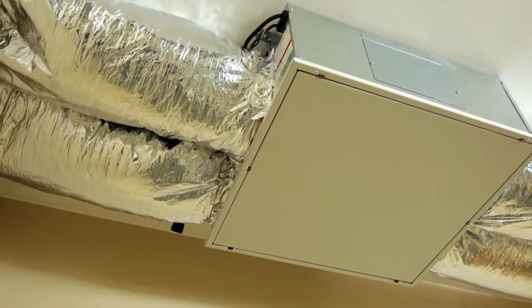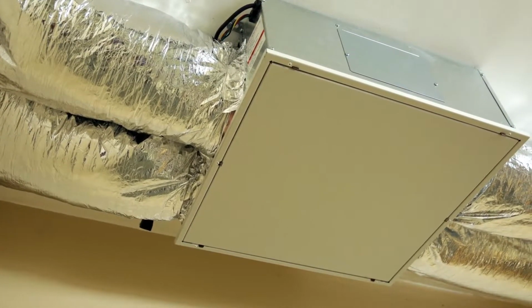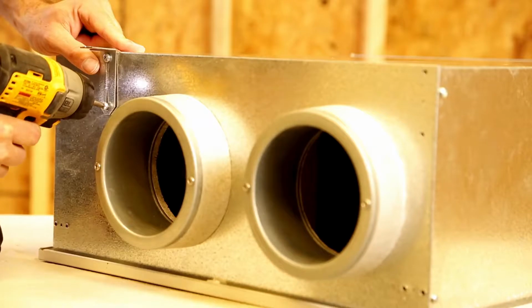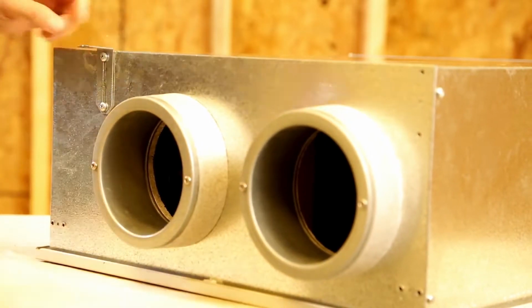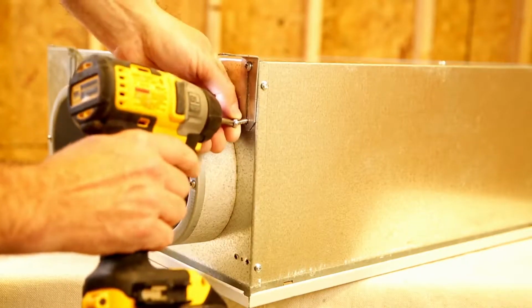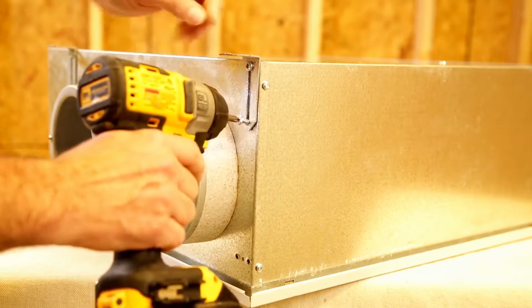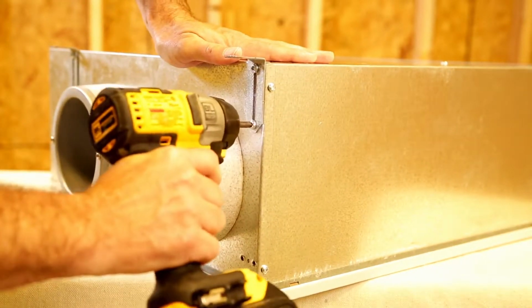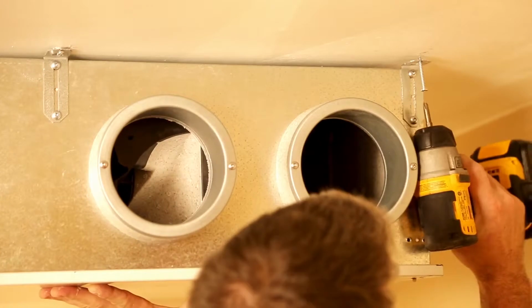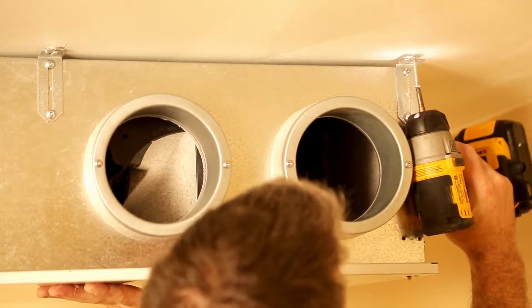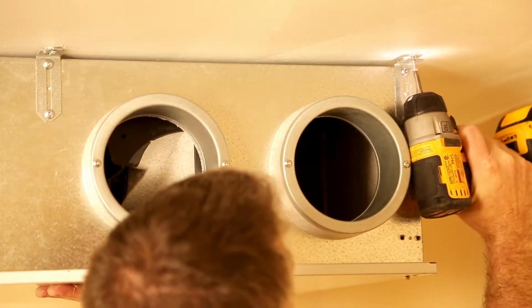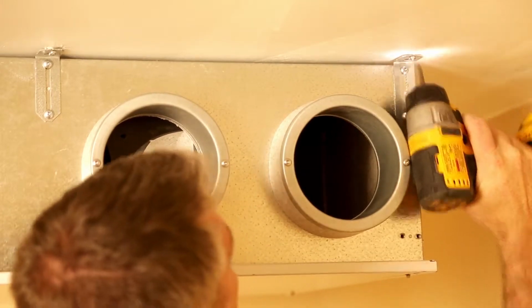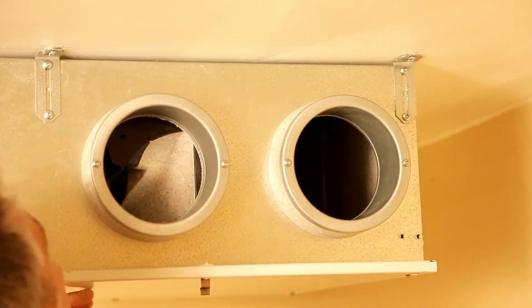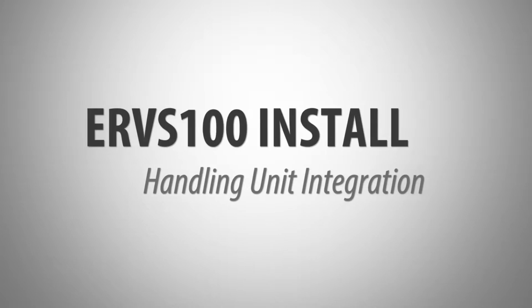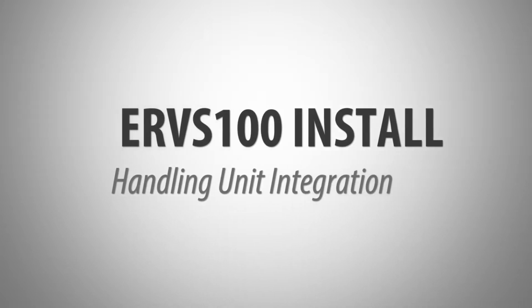If you're installing the ERVS100 under the ceiling in a closet or mechanical room, first mount the brackets to the bottom corners of the unit using two number 10 by 5/8 inch screws per bracket. The short side of the bracket should be oriented toward the top of the unit. Ensure that you secure the screws to trusses above the drywall, not into drywall alone. Secure each bracket to the ceiling using two number 8 by 1.5 inch screws per bracket.